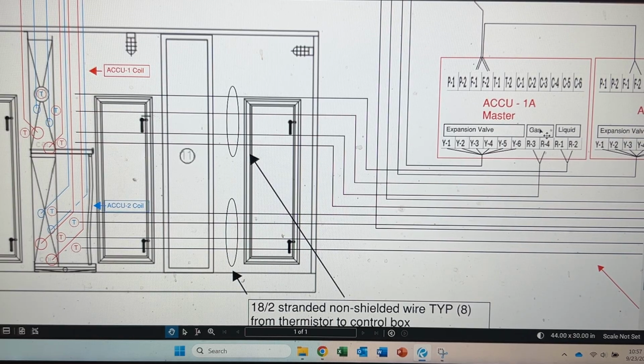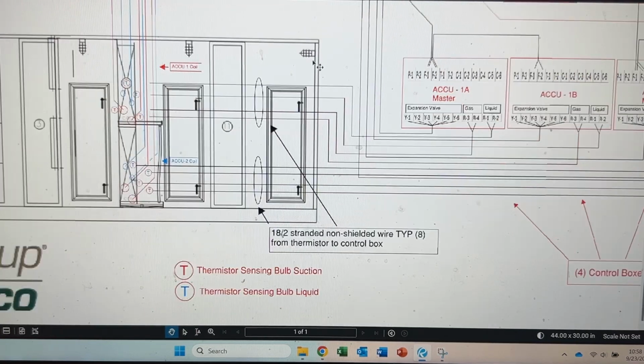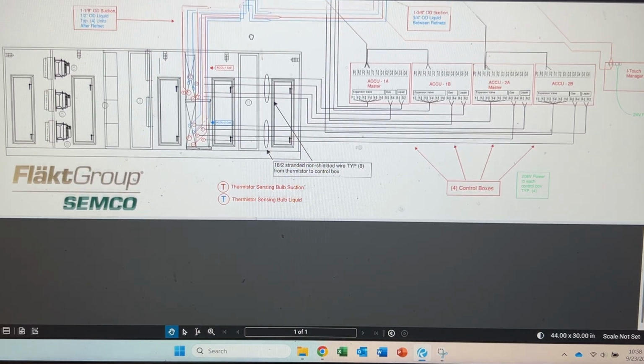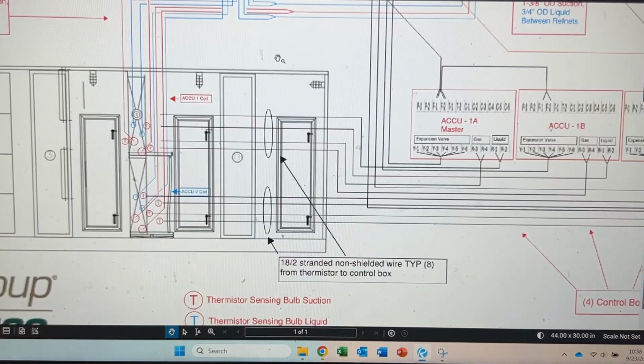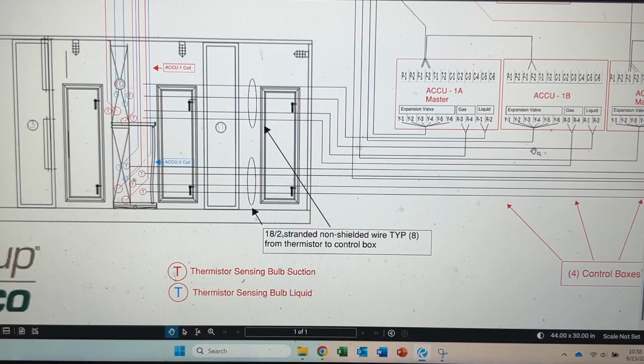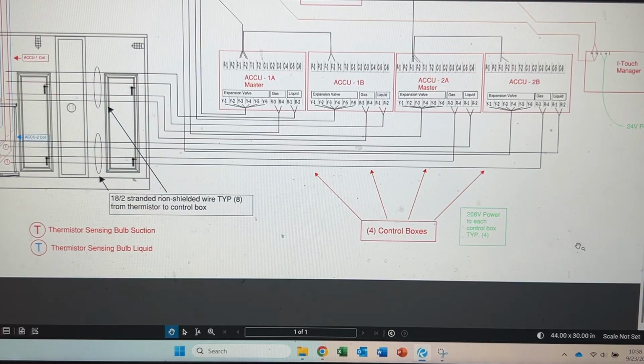On this drawing, I got suction on there, but it's gas. So these are the terminals for that, 18/2. So that's always monitoring what our delta is across that coil. So our liquid would be going into that through the coil and then out through here, and it's reading that and sending a signal to this expansion valve on what we need to do to help temper that air appropriately. So those sensing bulbs all terminate at these control boxes.